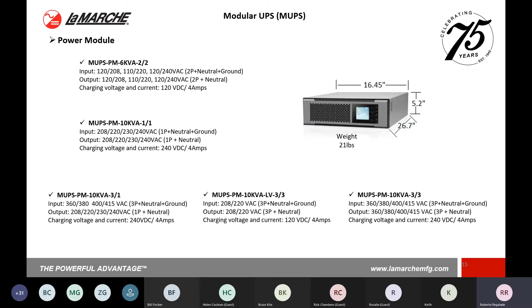And again, it's another thing you can really thank the technology of the modular UPS for. You're using high frequency technology. There is no big old transformer that you can put in there. These things are transformerless, I guess you can say, but there's still a style of transformer in there, not like you would see on your typical industrial UPS. Also want to note, you will see a little bit later on the battery, on the DC side, there is something special that I think does contribute to a much smaller package design for the power modules.